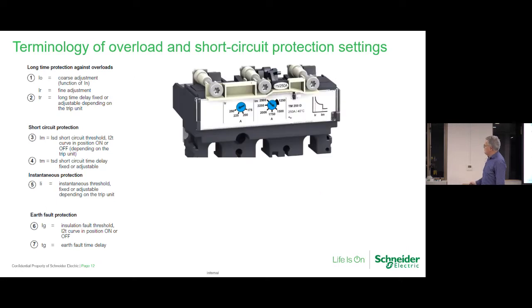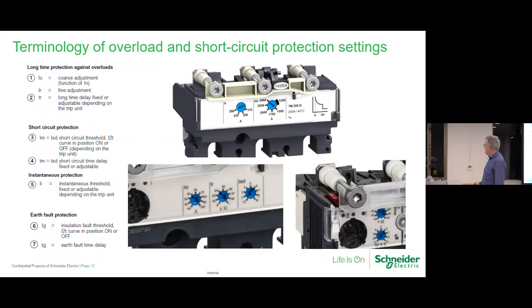I've brought this in, and I just want to show you these three types of trips, to give you an idea of the difference and what the contractor is facing. The switchboard builder is dealing with this every day of the week, and he knows what he's looking at here. But a contractor, the first time coming up there, if you haven't done a protection study, you haven't prepared them to say you must set this at this and this at this, then it's ready for failure, isn't it? Right at the beginning it's not a problem because you haven't got any loads connected or very few of them. But as time goes on, if these aren't set correctly, it is a problem, and often it always is in the early stages of the project.